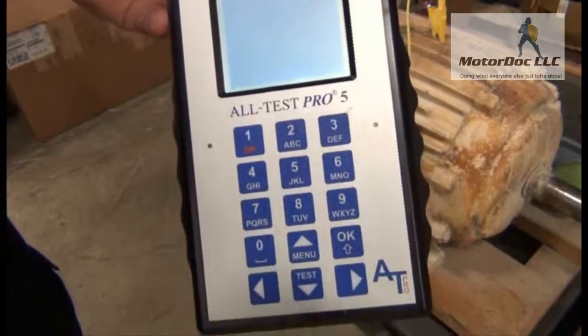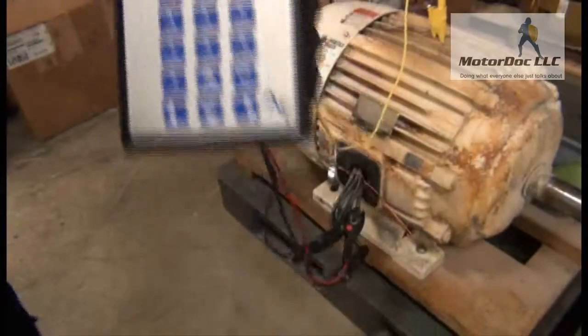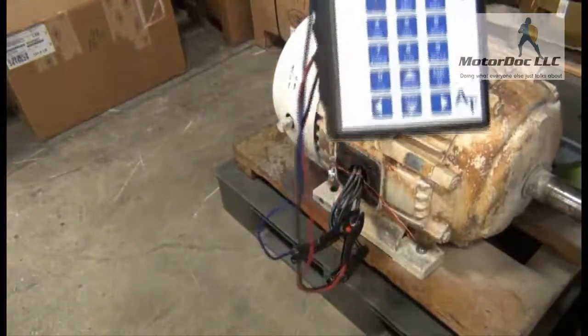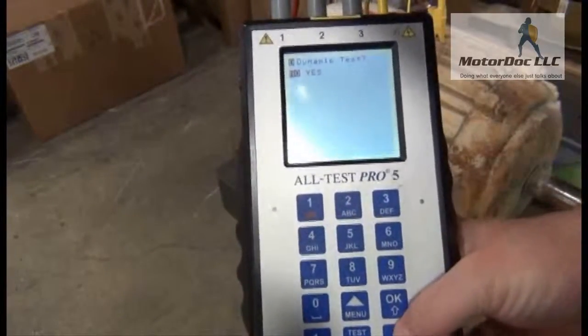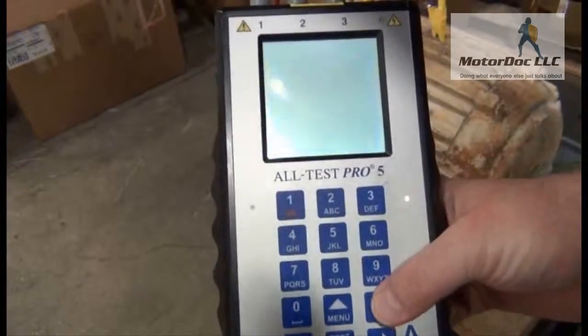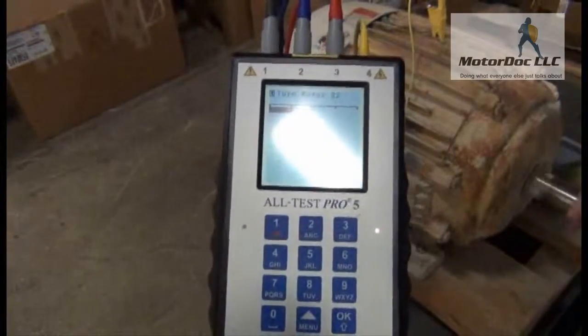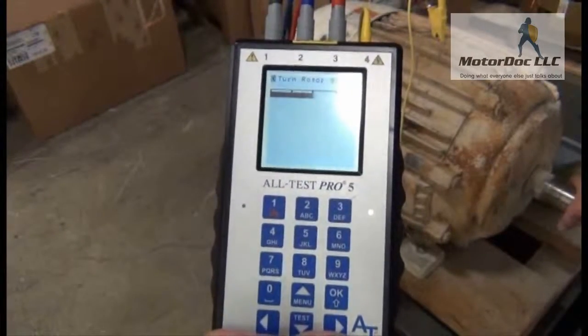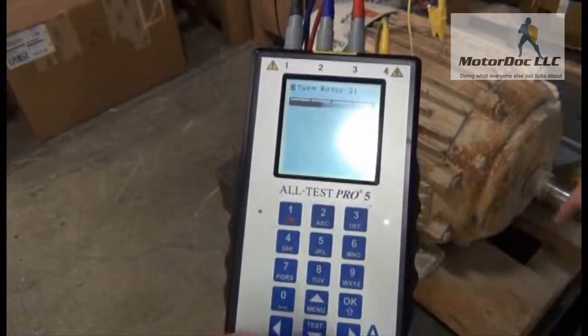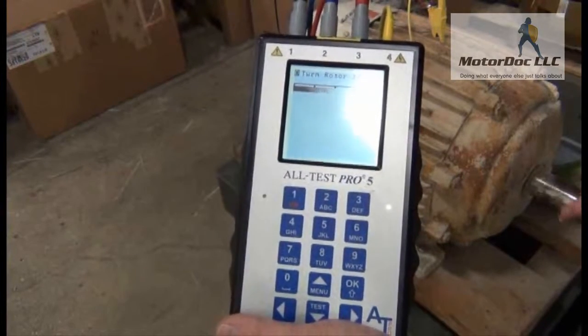As you can see, it does not take too long. The next one is a dynamic test. It's going to ask me if I want to do that. That particular test involves turning the shaft. So I'm going to select yes and select OK. Now I'm going to turn the rotor, and I need to turn it at a relatively constant pace. I don't want to start, I don't want to stop. And as you can see, it's going to flip through each one until it is done.